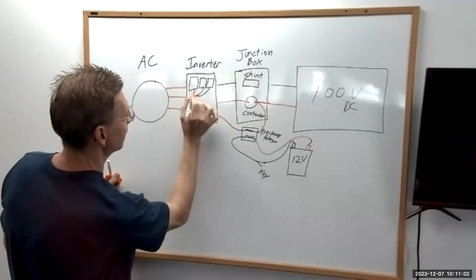Now, not drawn here yet, but we need to add two control wires that go from the contactor into the inverter. So when the inverter is happy, it saw the voltage come in, fill the capacitors, and sent the voltage back down this line, then the inverter energizes this contactor.